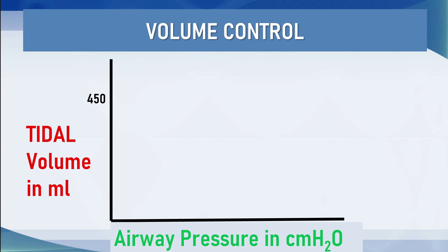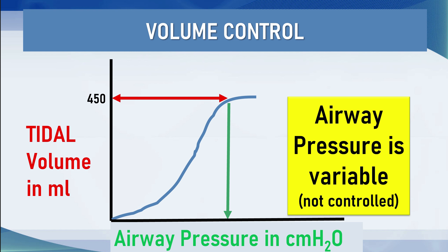So in volume control ventilation, a tidal volume goal is set — meaning the ventilator generates a flow of gas to hit the tidal volume target. In this case 450 mils is achieved, inward flow stops, and we can measure the airway pressure at end inspiration. That pressure is variable in volume control. The pressure is measured in centimetres of water; in this case the airway pressure is 20 centimetres of water for a set tidal volume of 450 mils.